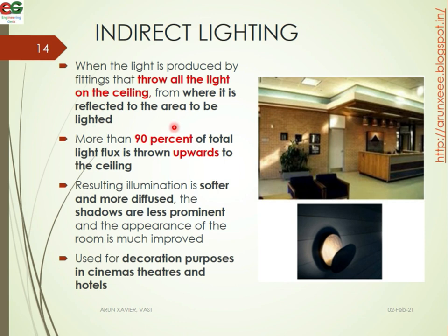In indirect lighting, the fittings throw all the light upwards to the ceiling, from where it is reflected to the area to be illuminated. More than 90% of the total light is thrown upwards to the ceiling, and the remaining 10% contributes to a softer, more diffused illumination. Shadows are less prominent.